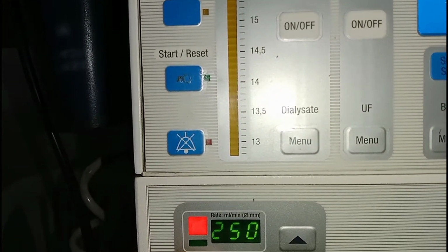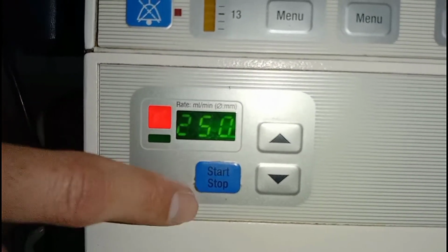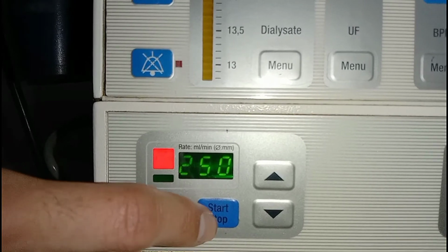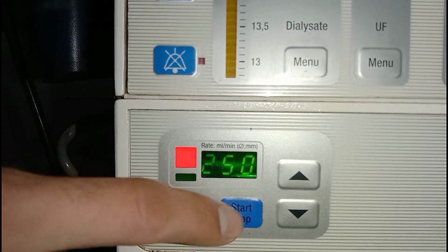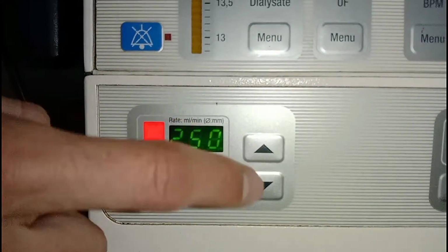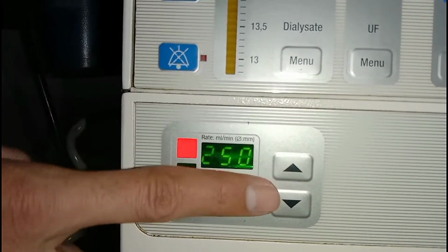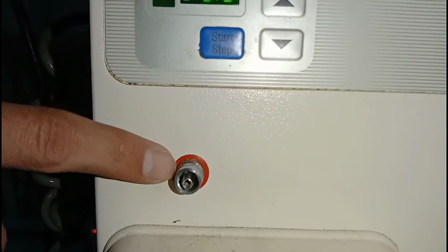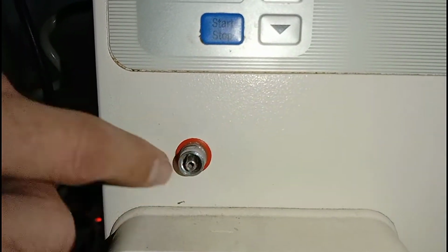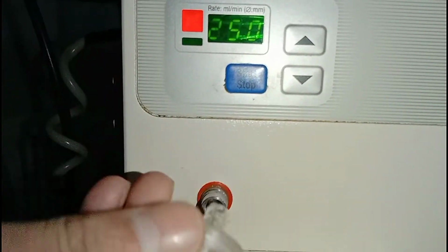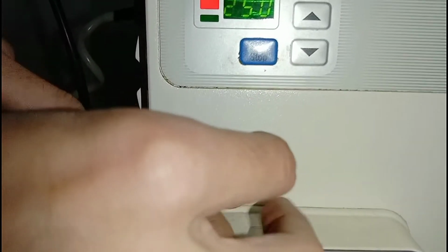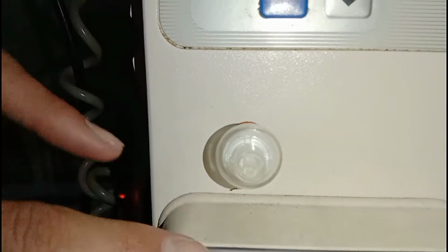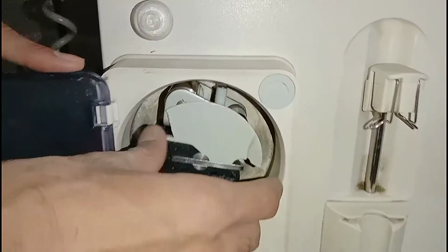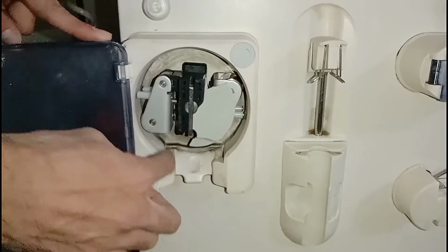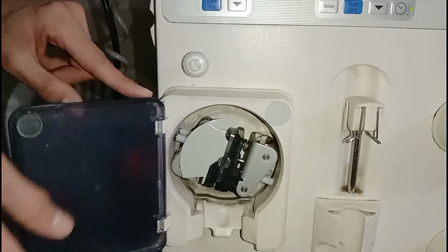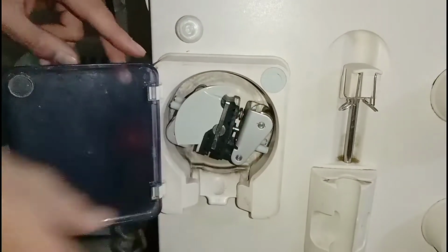Below this there is the start and stop button for the blood pump. The blood pump will start if you put this button on, and will stop if you put it off. These are the two buttons to control the blood flow rate. Below the blood flow rate there is P1. This will monitor arterial pressure, and here is a transducer, the transducer that is attached to this port P1. Below this P1 pressure monitor there is a roller pump that can also be rotated manually. This is the roller pump, and here is the sensor. If this gate is open, the pump will stop.